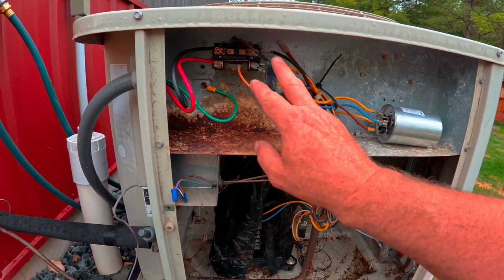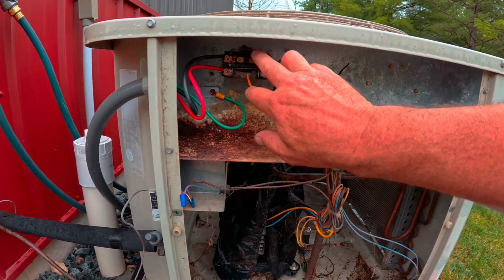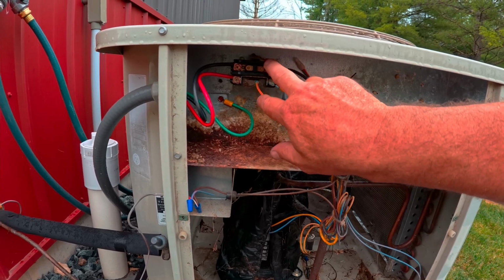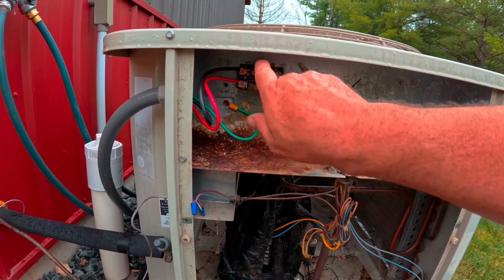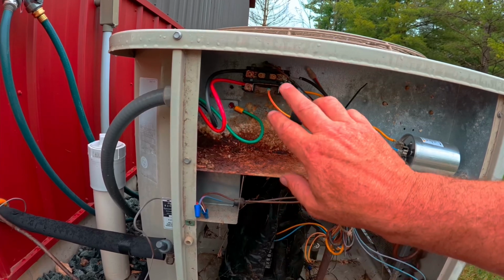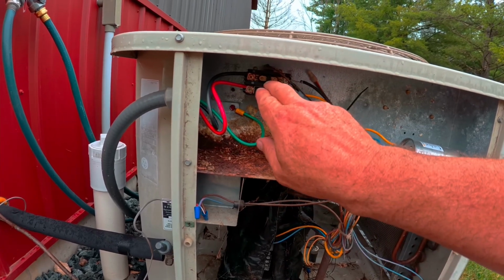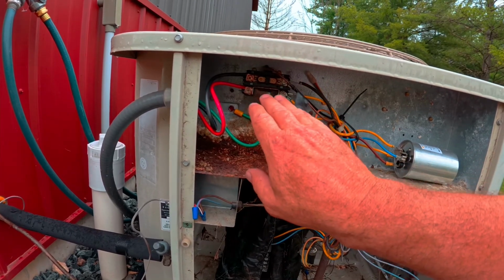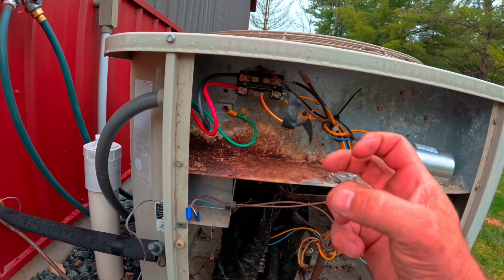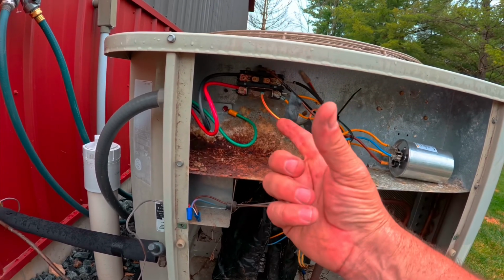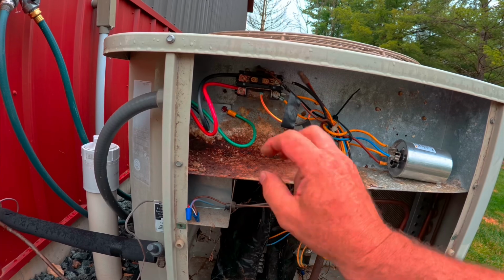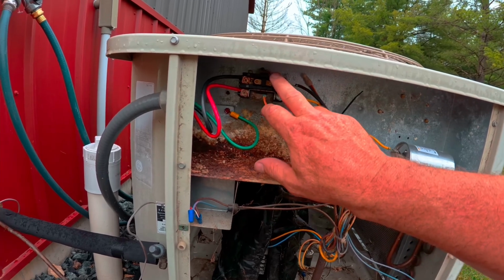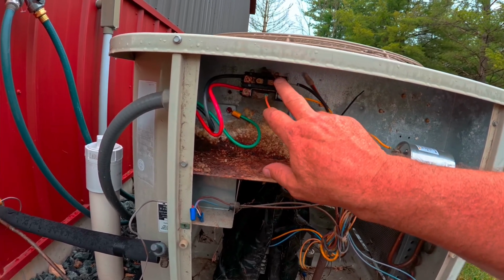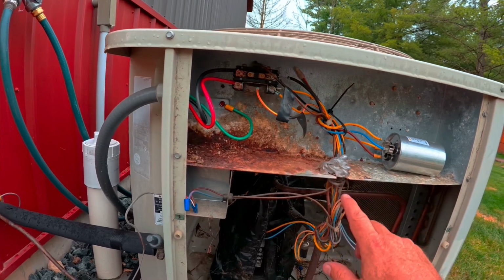So we got 2 scenarios. If you have 24 volts across the coil, the control circuit, at these terminals, 24 volts, and the contactor is not closing, that is telling us that the contactor is bad internally, and the coil is open, so therefore it cannot close the contact. If you do not have 24 volts across these 2 coil wires, that's telling us that we have a problem in our control circuit.